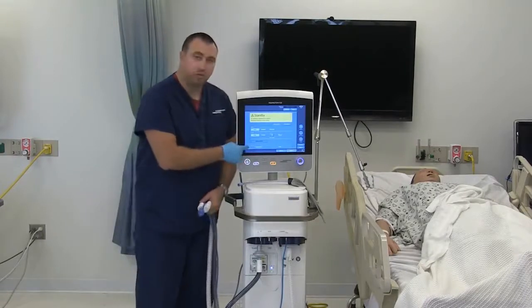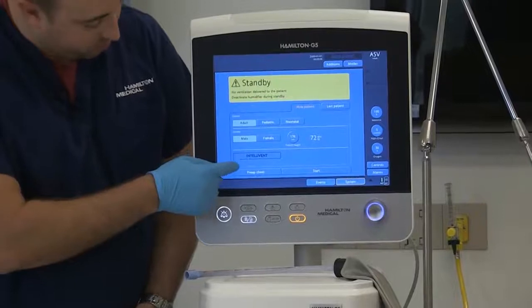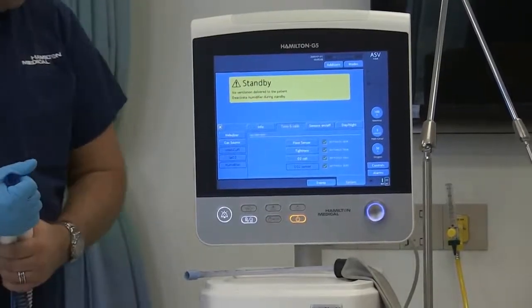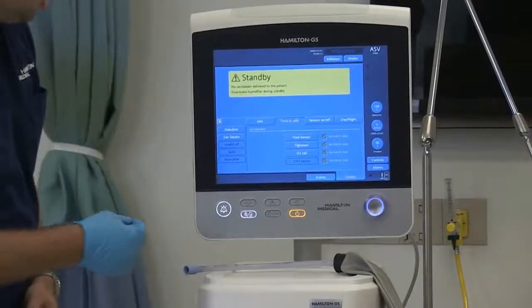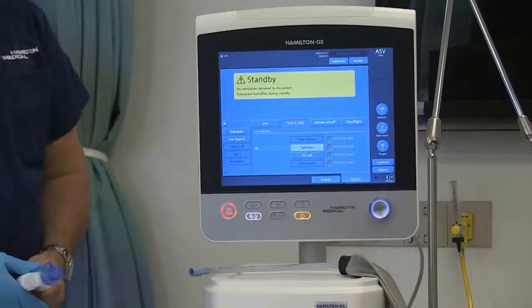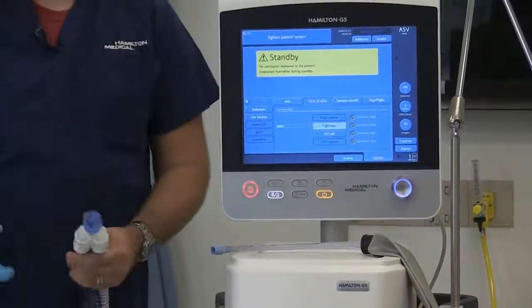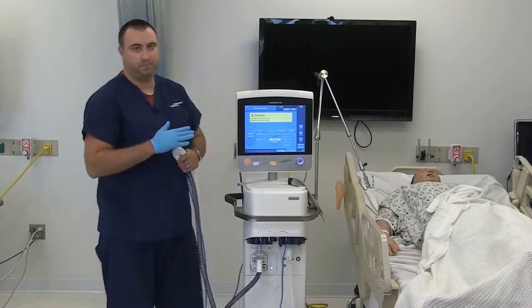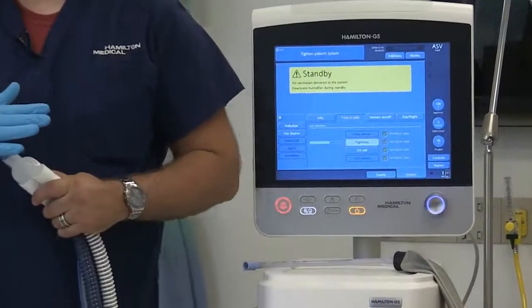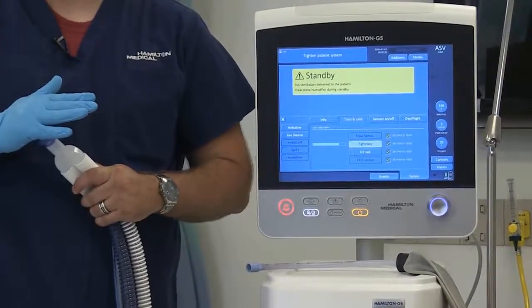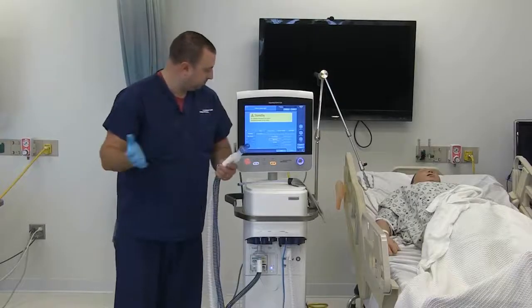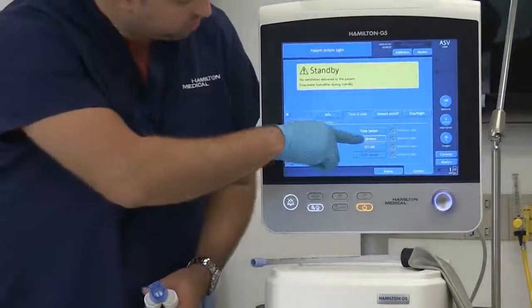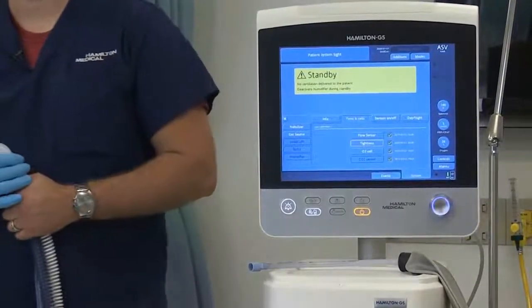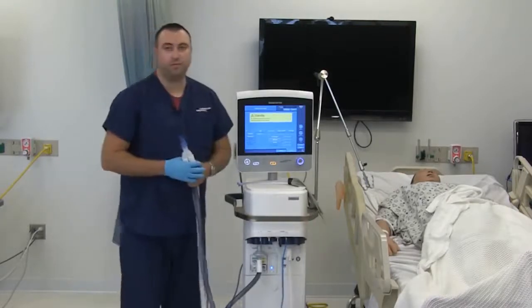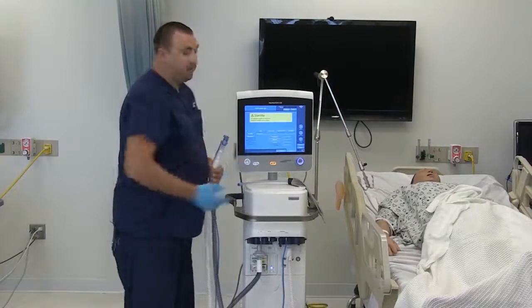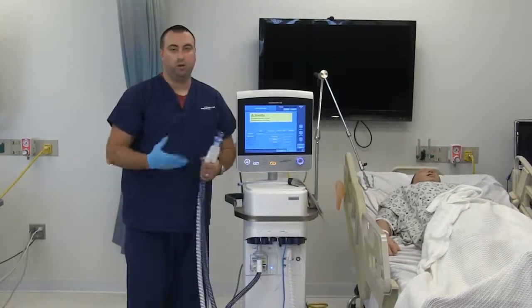The first thing you need to do before placing on a patient is the pre-op check. It's down here. So press pre-op check. So tightness, you do first. To do the tightness test, you press tightness test. Everything it wants you to do is going to tell you right here, tighten patient system for instance. So you just plug your circuit up. And it takes about 20 to 30 seconds to perform the tightness check. Patient system is tight. You also get a green check mark and a date and time in which the test was passed. This will carry over even if you shut the vent off and turn it back on. All of this data on when each pre-use check was completed will populate again.